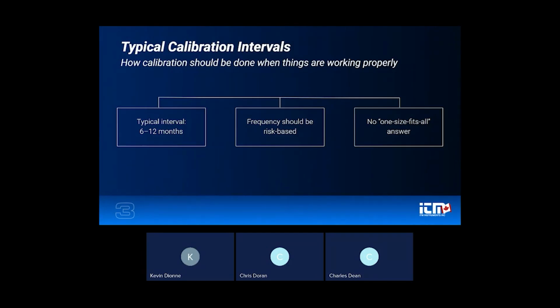At the end of the day, calibration should not be driven by calendar. It shouldn't be driven by any set date because there's no one size fits all answer to this. The right frequency is risk-based. It depends on how critical your measurement is, how often the instrument is being used, and the environment that it's operating in. So the key takeaway here is there's no one size fits all answer. Two gauges could look identical on paper, the same model, but they can require two very different calibration intervals once they're put out in the field based on these external factors.